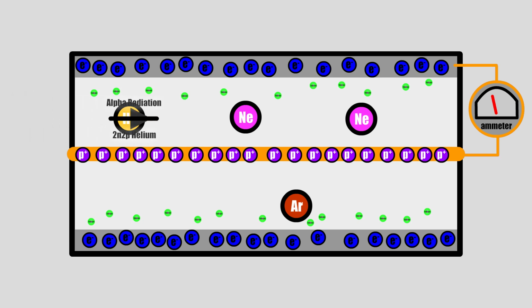The Geiger counter measures the intensity of high-energy radiation such as alpha, beta, gamma, and X-rays in an environment. It does this using quantum mechanics and electricity. First, a vacuum environment is needed to allow the chamber to be filled with the desired gas. One side of this environment must be made of a material that allows the radiation to pass through. In this way, radiation can enter the environment while preserving the vacuum structure.